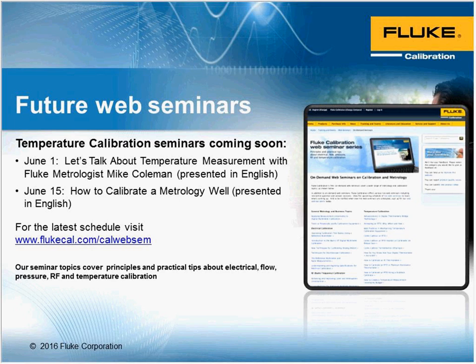Question comes from Randall. When checking these surface probes at around 65 degrees Fahrenheit to 90 degrees, what do you use as a source, and what probe would you calibrate them with? We use any chamber with a Fluke 5628 and STD probe, and Omega surface probes wrapped in aluminum foil. Okay.